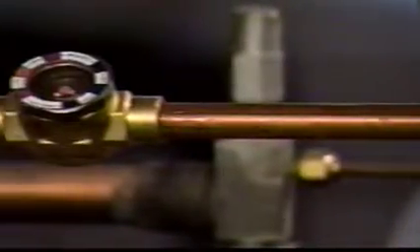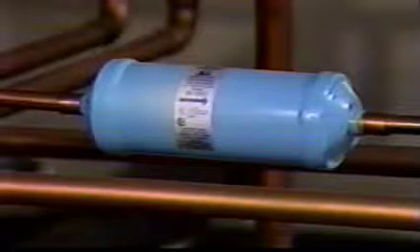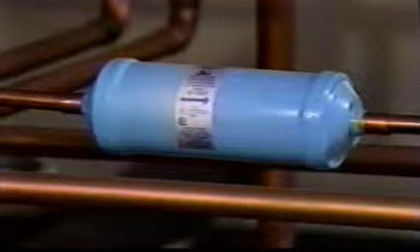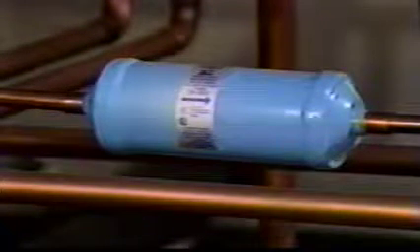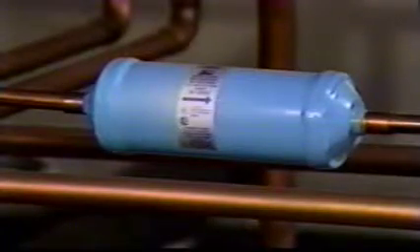Eventually, flow will stop. Any water that is dissolved in the refrigerant must be removed before the refrigerant gets to the valve. It is the job of the liquid line filter dryer to remove any moisture that entered the system at installation or after the system became operational. Liquid line filter dryers are used in almost every cooling system that uses refrigerant.